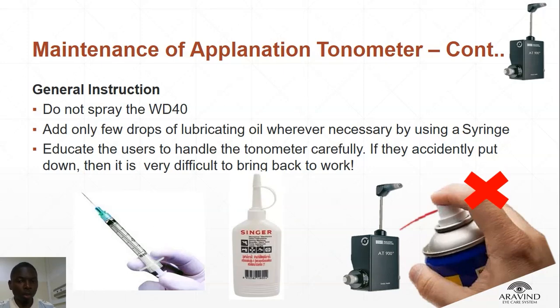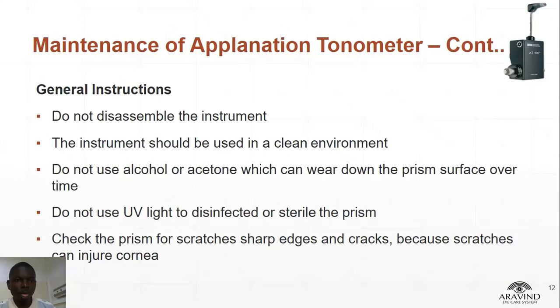Do not spray WD-40 on the parts of the tonometer. Add only a few drops of lubricating oil wherever necessary by using a syringe. Educate the users to handle the tonometer carefully. If they accidentally put it down, then the inner part of the tonometer gets damaged and it is very difficult to bring back to work. More on general instructions. Also, do not disassemble the instrument. The instrument should be used in a clean environment.